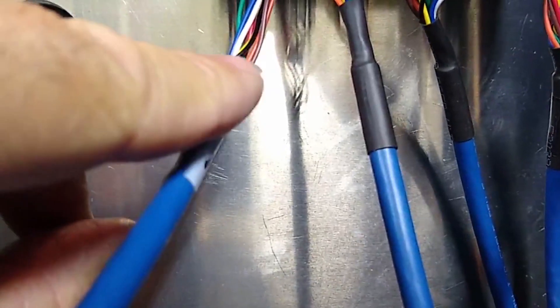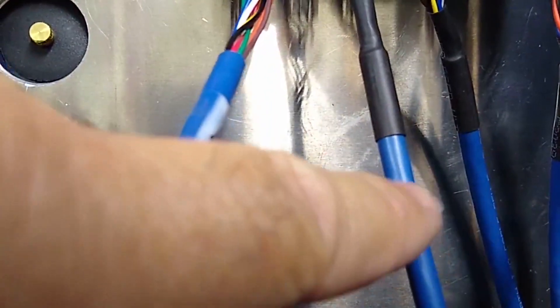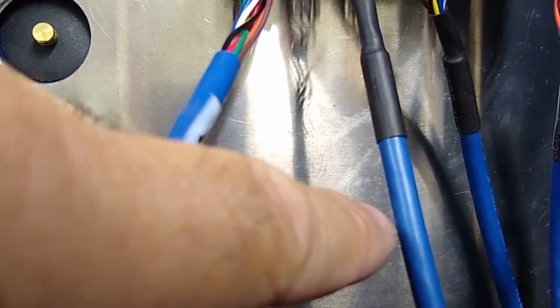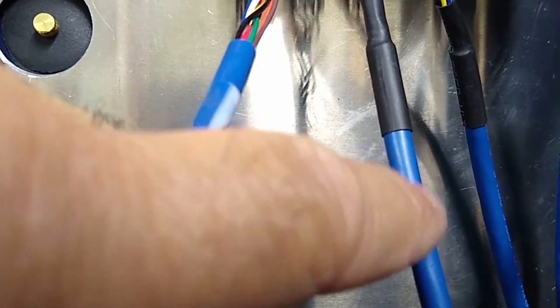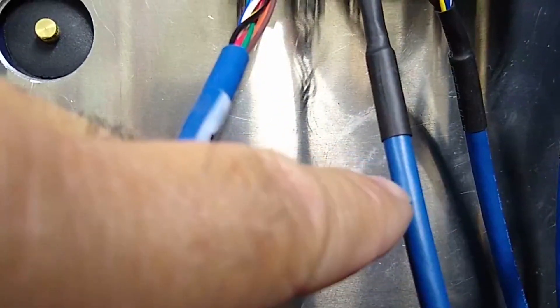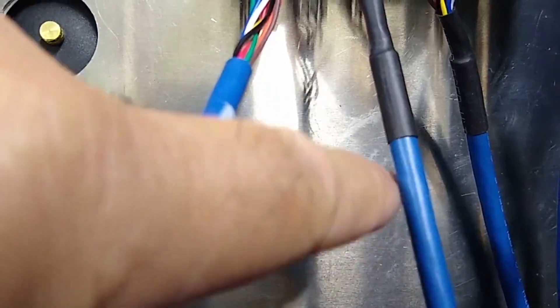You do not have to go all the way through, and you do not want to nick these wires. Then you can lightly score around the cable to remove the rest of the jacket. What I mean by score is don't go all the way through—just barely with the razor, go around that jacket, score it, then peel it off and it'll tear away.